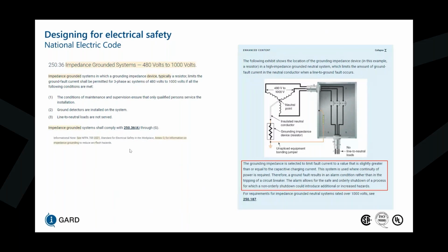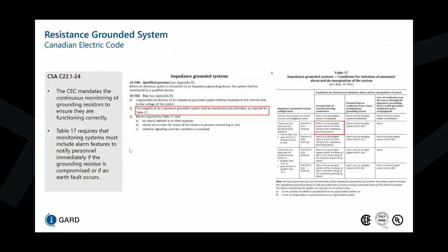Now, when we compare this to the Canadian Electrical Code, we can see that we've had a lot of changes starting from 2018 to 2021 and then to 2024. 2018 is where they introduced impedance grounded systems in Section 10 on grounding and bonding. And Rule 10-302 indicates that the integrity of an impedance grounded system shall be monitored and controlled as required by Table 17.